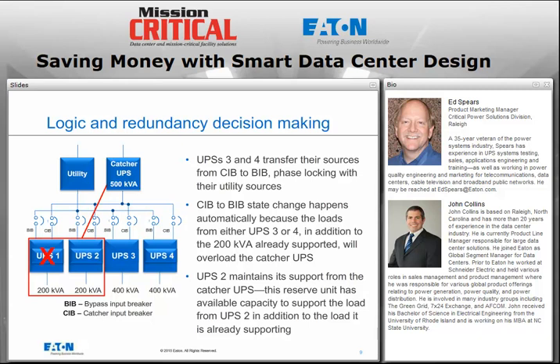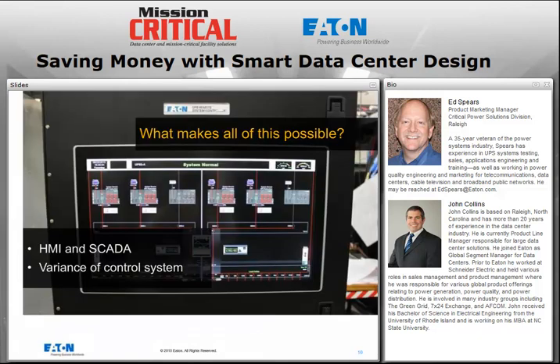So as you can see, there are lots of different scenarios, and the user would like the flexibility to not have all the primary UPSs be the same size. They'd hate to, for example, have to have 4 500 kilowatt UPSs when what they really need is a 200 kilowatt, a 50 kilowatt, a 500 kilowatt, and a 1 megawatt, for example. So it would be much better to have some flexibility there. And keep in mind that the decision making is not based on the rating of the UPS, but on the load that we sense on the output of each UPS. So we're looking and saying, where are the loads, how big are they, and who's going to be in the club to be supported by the catcher, and who is going to be supported by traditional bypass operation. So hopefully that drawing helps clarify a little bit what's going on in the logic here. Okay, moving on to the next slide.